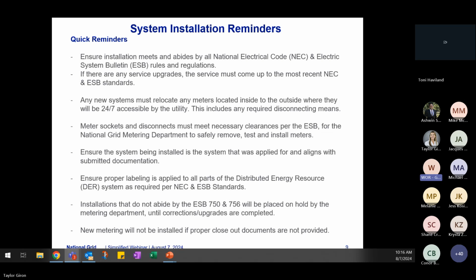Ensure that all proper labeling is applied to all parts of the DER system as required by the NEC and ESB. Any installations that don't abide by all of our codes are going to be placed on hold by the metering department until corrections are completed, and any new metering won't be installed if proper closeout documents aren't provided.